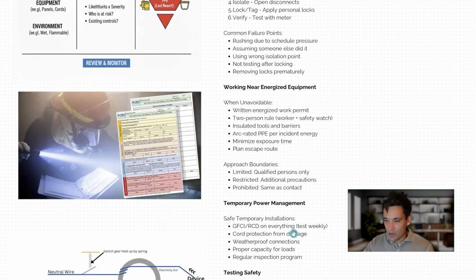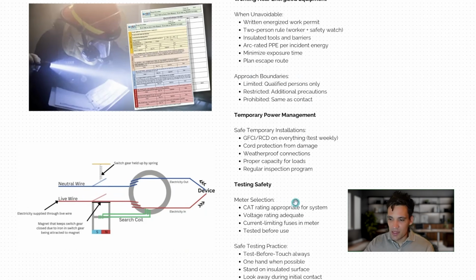Final thing I want to talk about is temporary power management. It's often quite a challenge on construction projects because you need temporary lighting, and people need power equipment and tools. There often ends up being quite a significant amount of temporary electrical works. The principle behind these is that you have RCD devices fitted on everything, and that systems are properly designed and installed by competent professionals, i.e. electricians. An RCD, the way it operates, is that you have a normal electrical system with an active and a neutral. An RCD is a very sensitive device that measures if there's any difference between the active and the neutral, so there's current leaking somewhere.